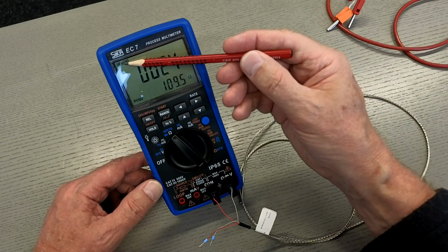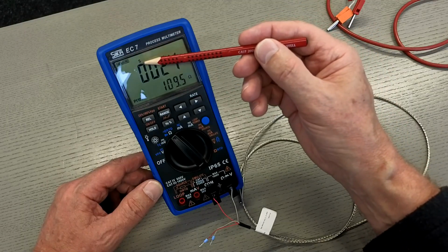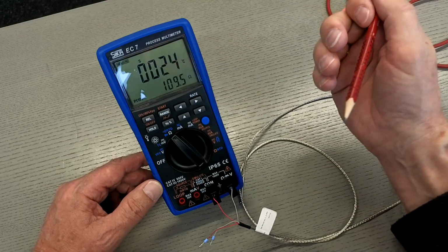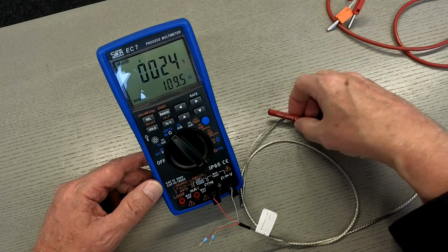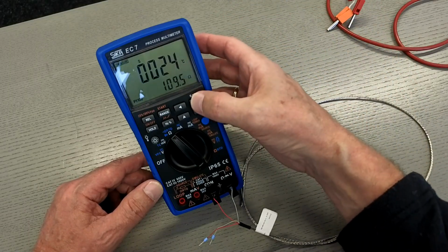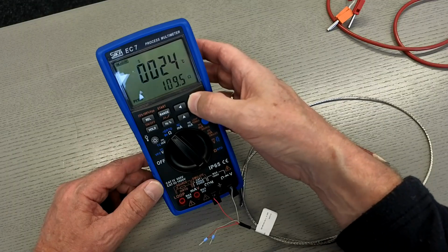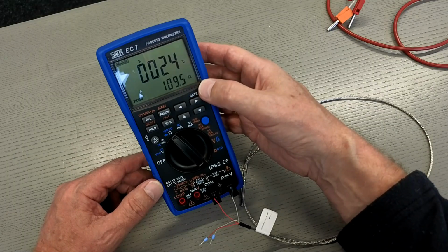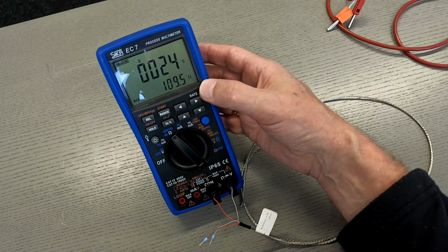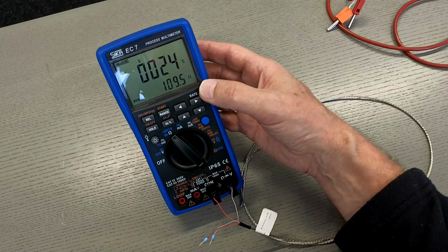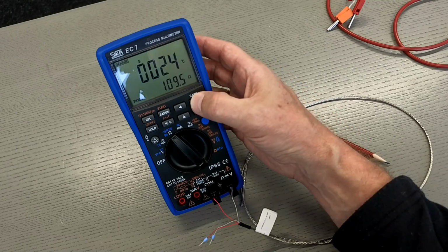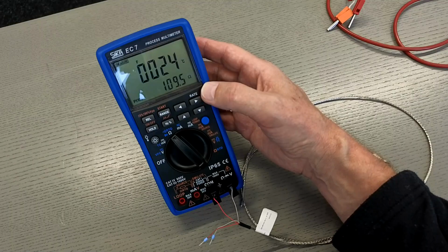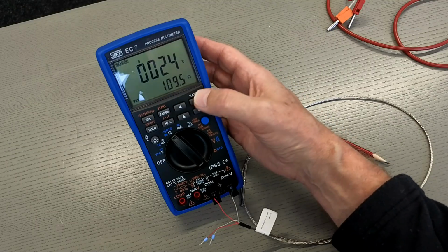Of course, we make a measurement, and we see additional information, the speed of the measurement. I can change the speed from S to F. F means fast and S means slow. Slow means we have a measuring time of 200 milliseconds, that means we make 5 measurements per second. If I change over to fast, then I make 20 measurements per second. That means we have a measurement rate of 50 milliseconds.